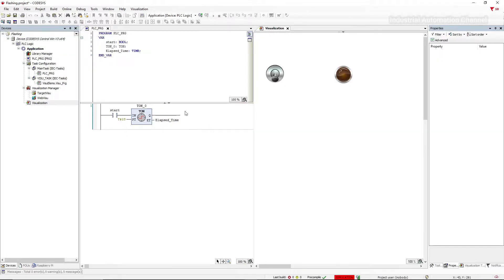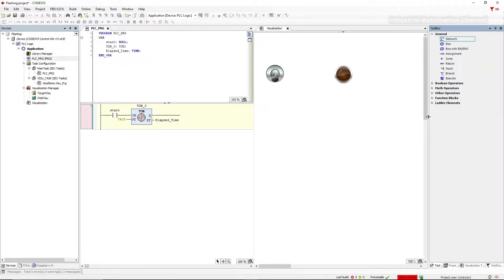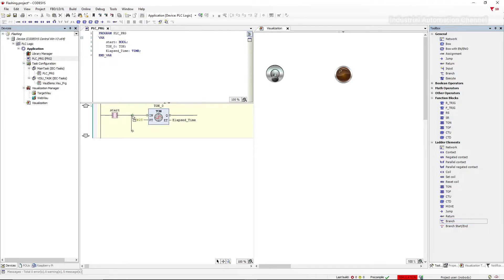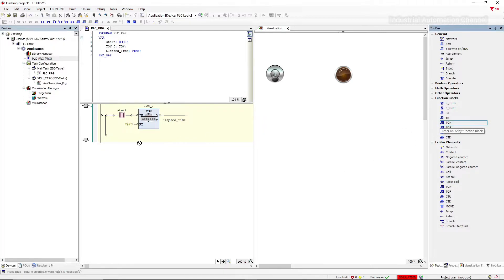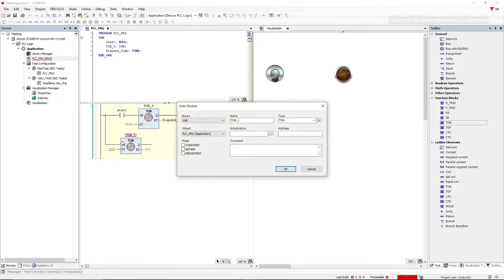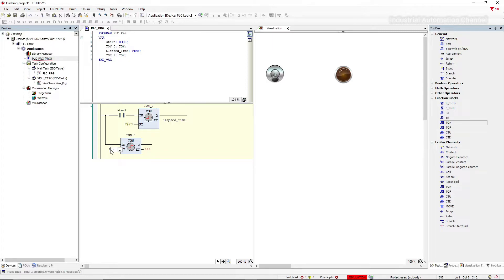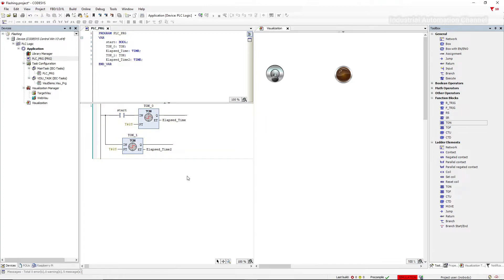So I need another timer to produce an off signal and reset the first timer. This timer will be activated when the output of the first timer after 2 seconds is on. So I insert a contact before the second timer. The output of the first timer will be the input for the second one.